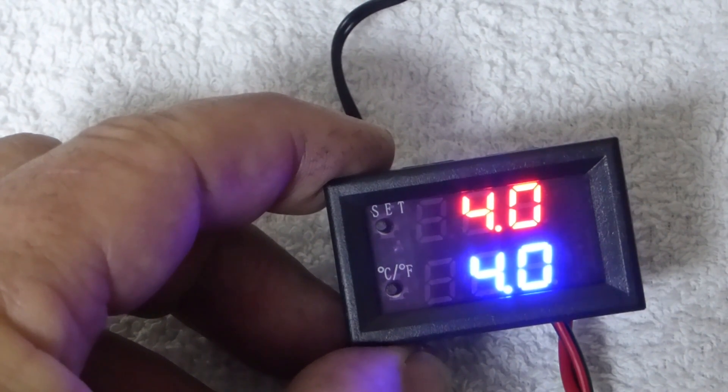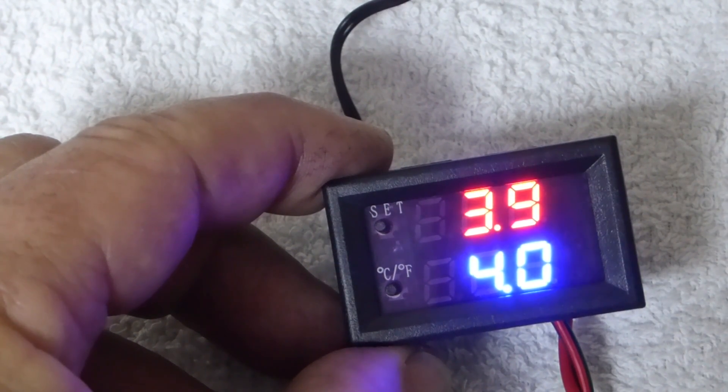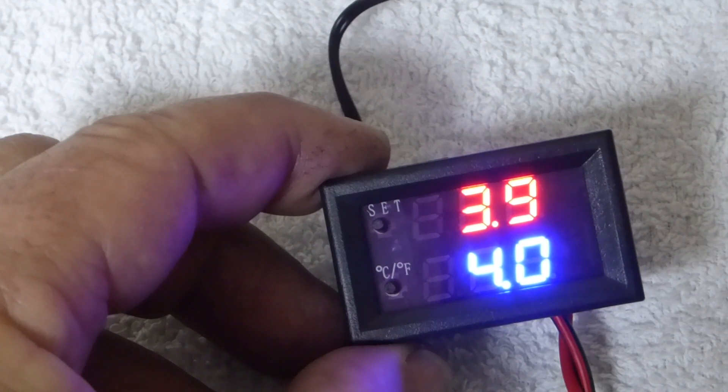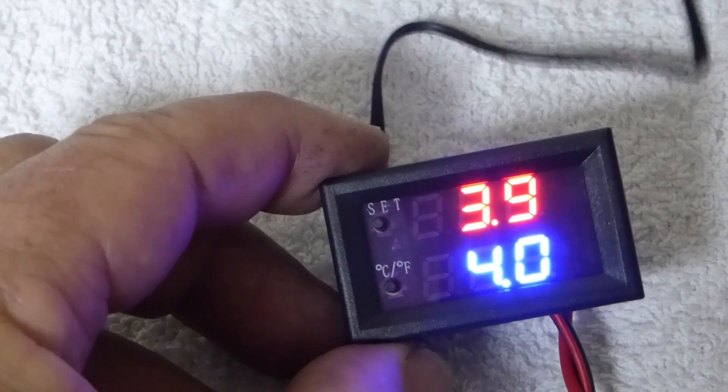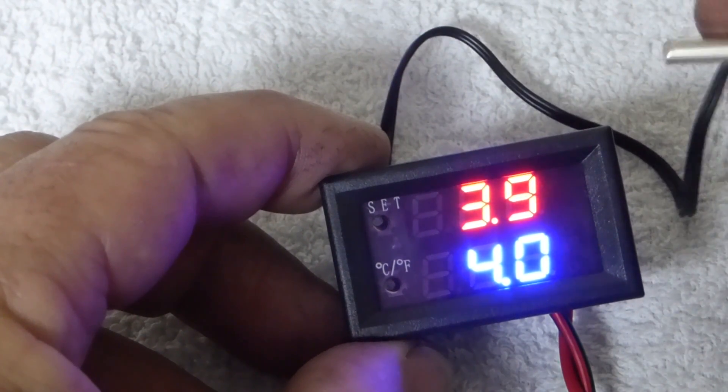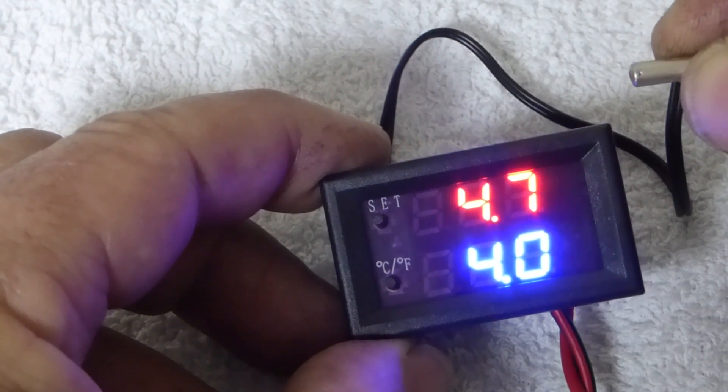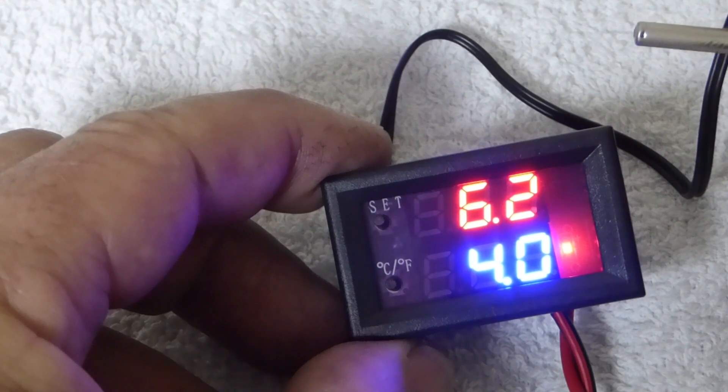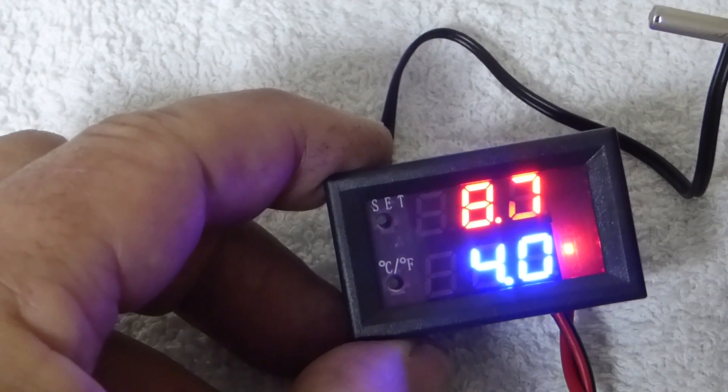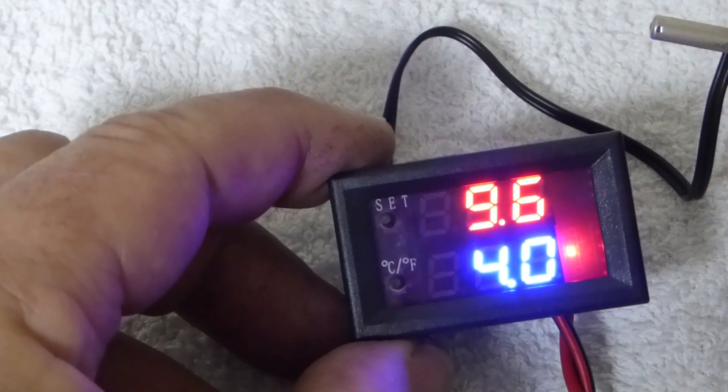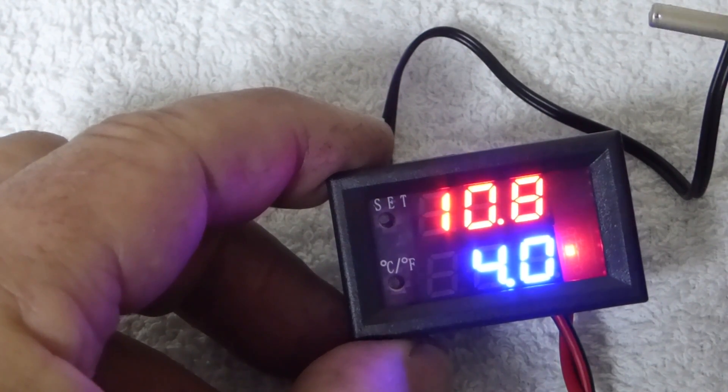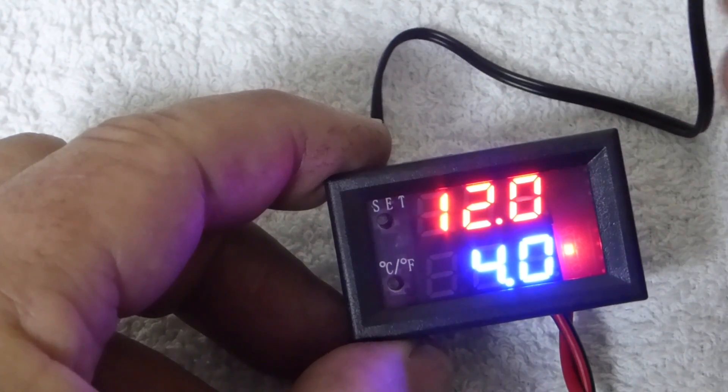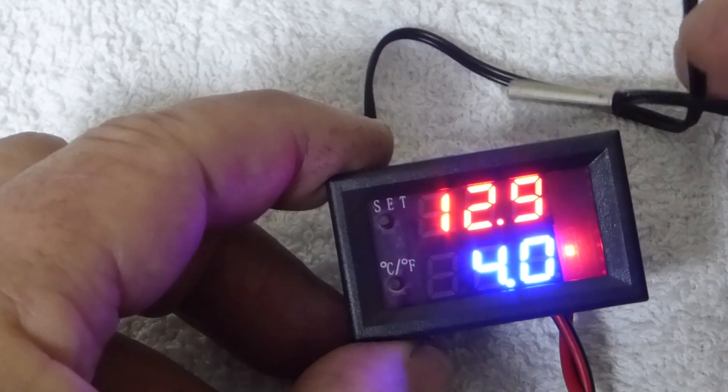There you see the temperature down to four and it switches off. Now if I hold that probe in my fingers, you'll see the temperature go up and when it hits six degrees it turns the compressor back on. So there's a two-degree difference.